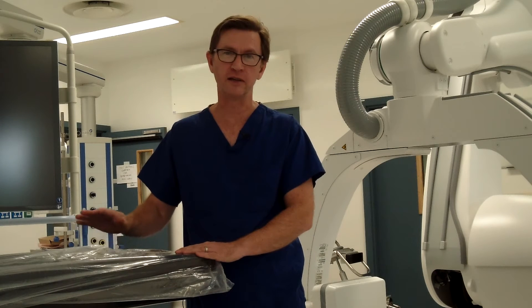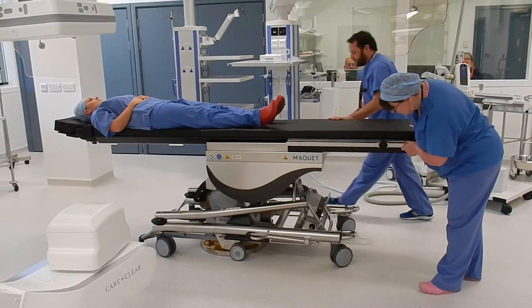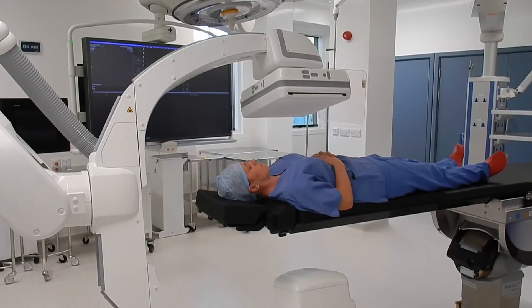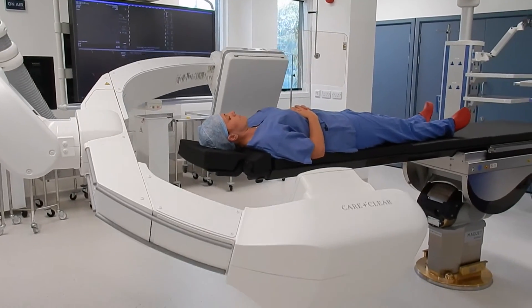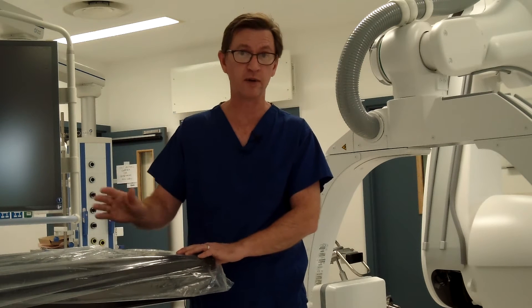One of the other features of the hybrid is the operating table — in this case a Maquet table. It's carbon fibre and completely radiolucent, so X-rays can be shown through the table almost the entire length, with the exception of the metal footplate.